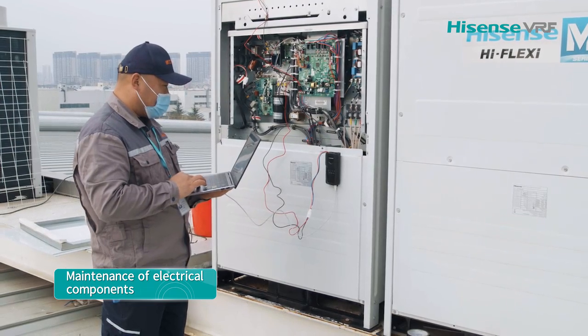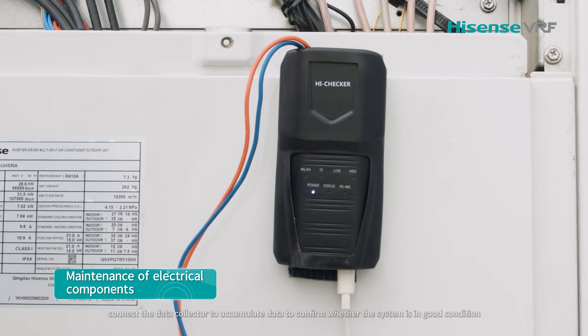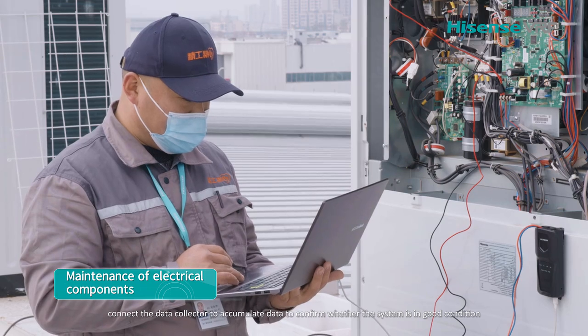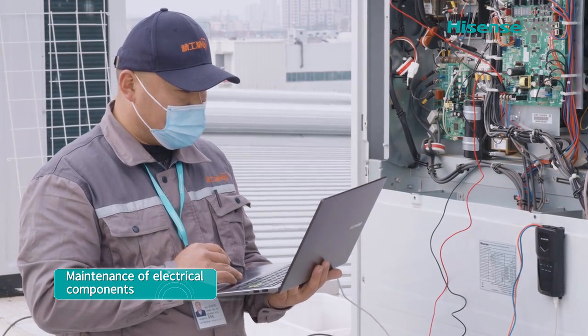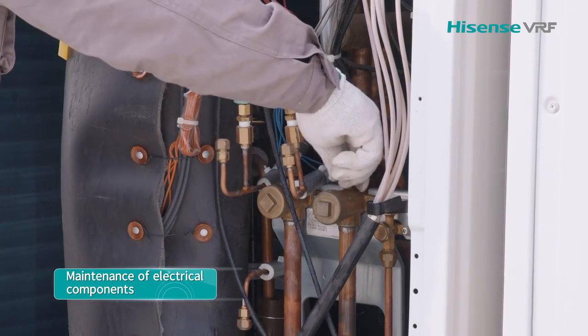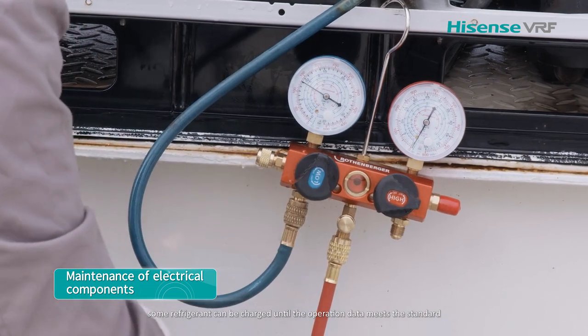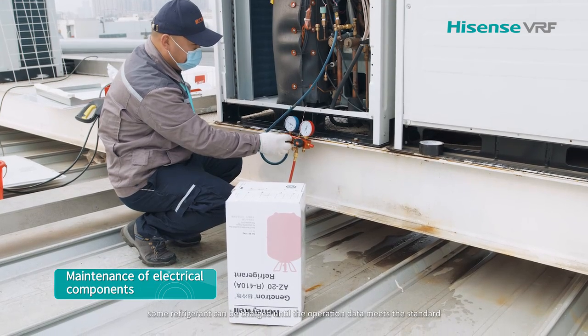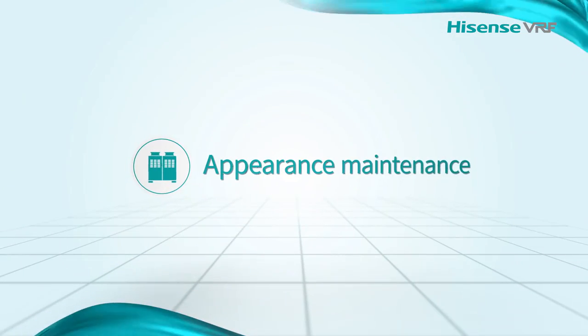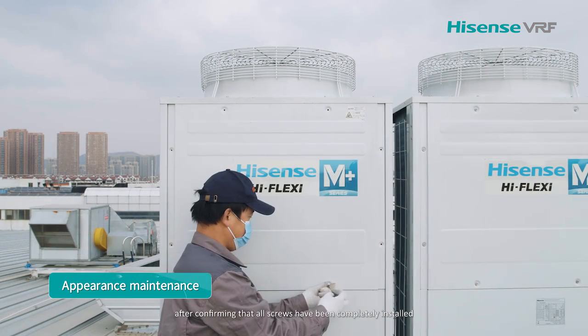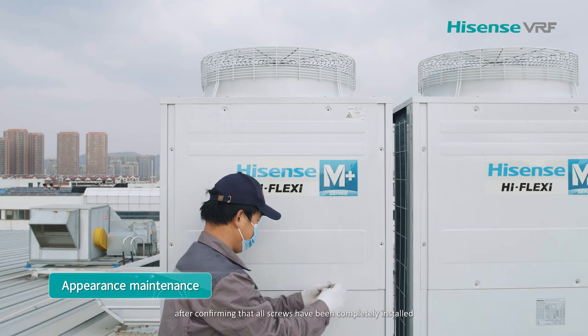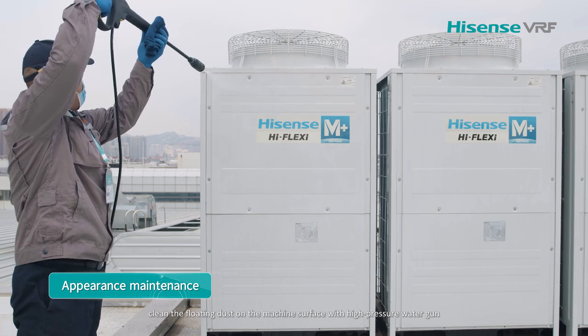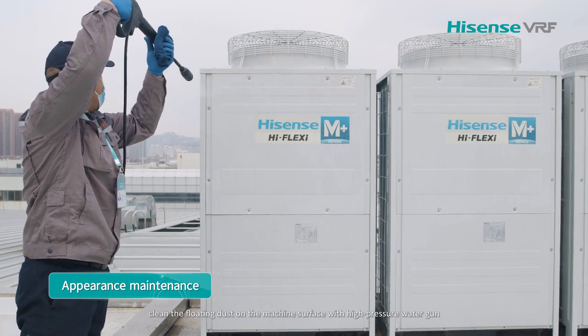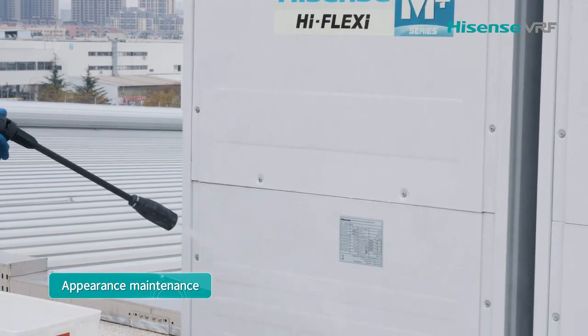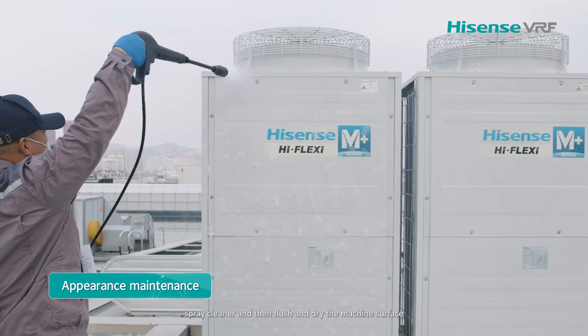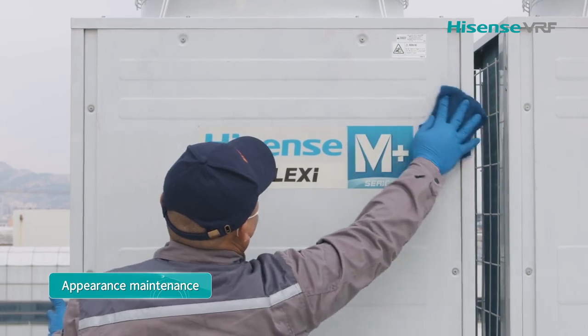Test the whole system. Connect the data collector to accumulate data to confirm whether the system is in good condition. If there is leakage in the system, some refrigerant can be charged until the operation data meets standard. After confirming that all screws have been completely installed, clean the floating dust on the machine surface with high pressure water gun, spray cleaner, and then flush and dry the machine surface.